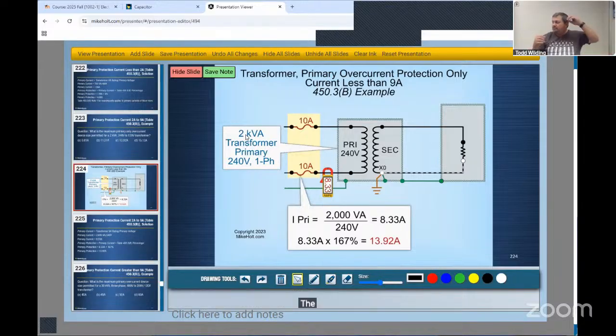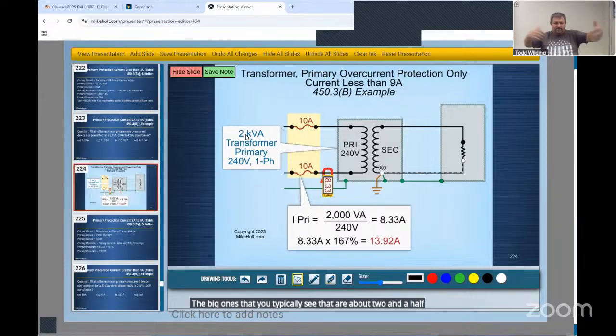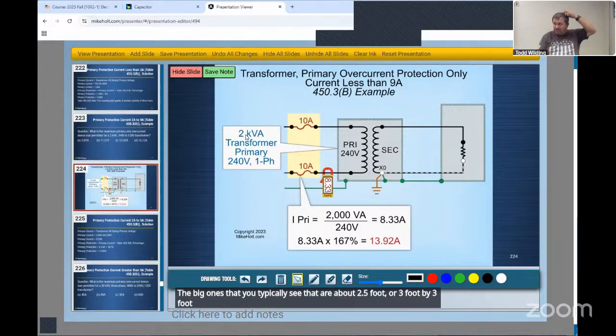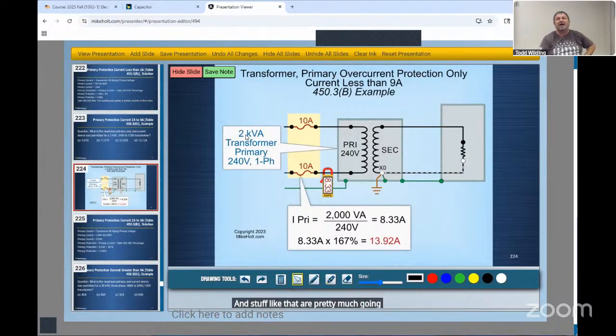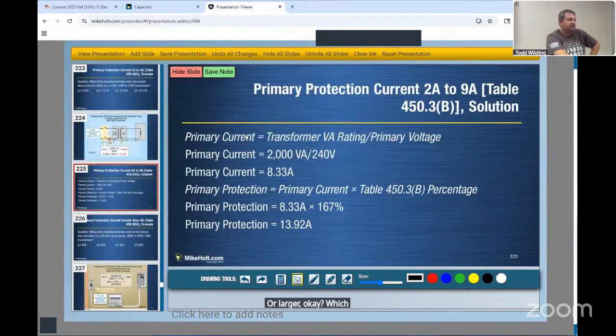Again, small transformer, 2 kVA, not very big. The big ones that you typically see that are about 2.5 foot or 3 foot by 3 foot, the big ones you see in commercial and stuff like that are pretty much going to be a 75 kVA or larger. Okay. Which would be the next one. So here's your formula. 2000 divided by 240, 8.3, multiply that by 1.67 gives you 13.92.